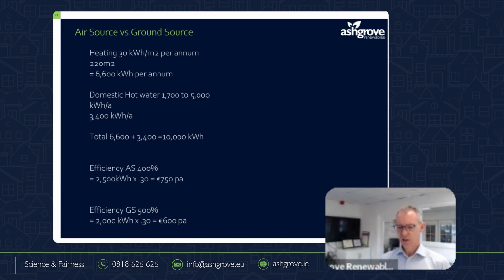The question then is, if I'm spending €2,000 or €4,000 or €5,000 to save €150, is that a good decision? Some people will say, I don't want the air source unit out the back. I'm happy to spend €5,000 to have that gone. The ground source unit, of course, sits in the utility room or wherever it is. But of course, the bigger that house gets, or if it's a commercial building, the bigger that difference becomes in savings, and then it might become more meaningful. But people asking us today for ground source heat pumps because they don't want to go air source, when we investigate, it's because of running costs. But the running costs, as you can see here, in this case at least, is not the right reason. There might be cases where it is the right reason, by the way.